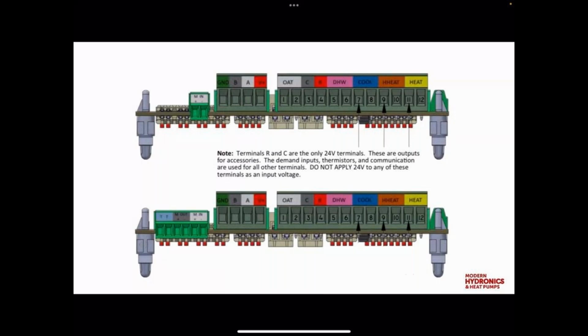So if we're in the space heating mode or in the domestic hot water mode, we've run for X number of minutes and we're still not reaching our target temperature. So then we're bringing on the backup. Now, true to form, just as we bring on the backup, we also will fold the backup off on the other side of that. In a lot of cases with heat pumps, sometimes they need a little boost and a lift to get up to the desired target water temperature, but then once they're there, they can sustain that temperature. And so then we will back off of either the electric element or the boiler.